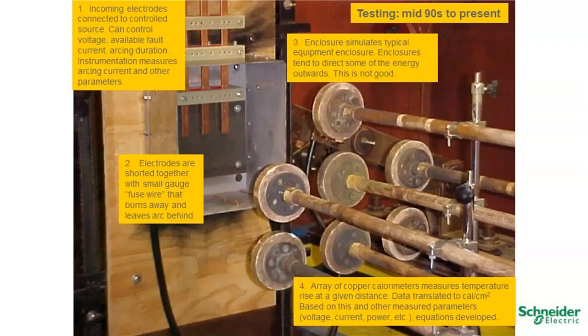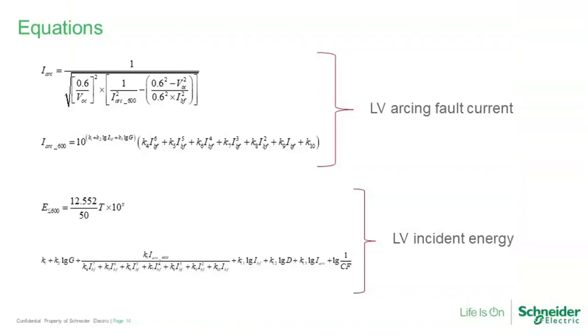Again, I'm going to speed through some of the details here, but basically, we set up enclosures that approximate a typical piece of power distribution equipment and hook it up to a source where you can control the voltage and the amount of fault current available. Round discs in front of the enclosure are calorimeters, which measure the heat rise produced by the arc flash event. You do that a few hundred or a few thousand times, and before long, you've got a pretty good calculation model. This is exactly what was done in IEEE Standard 1584, the IEEE Guide for Arc Flash Hazard Calculations.